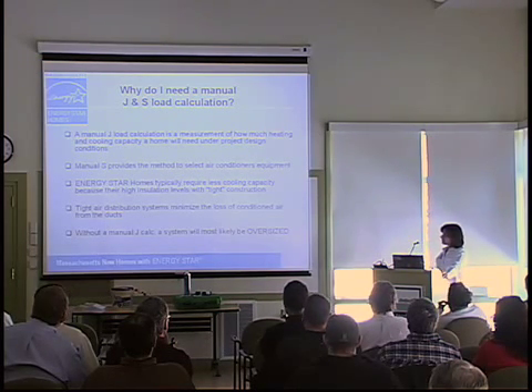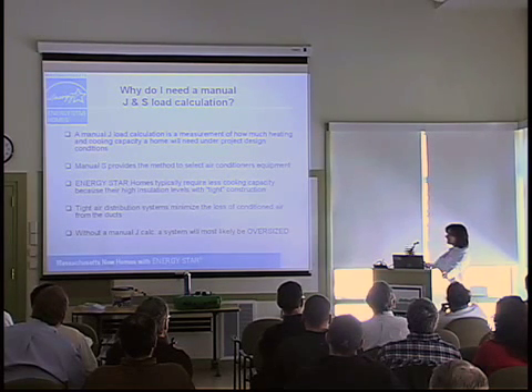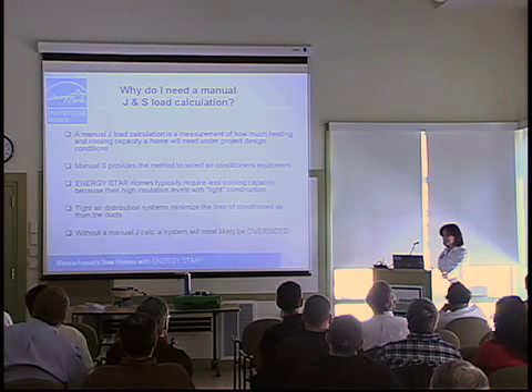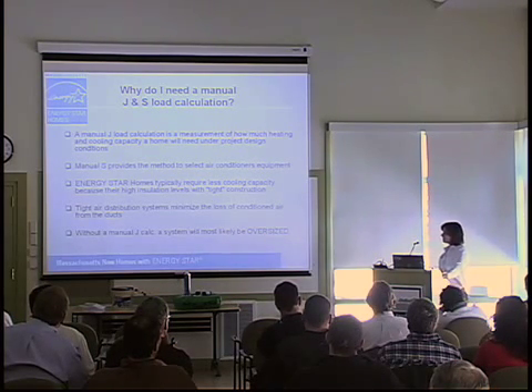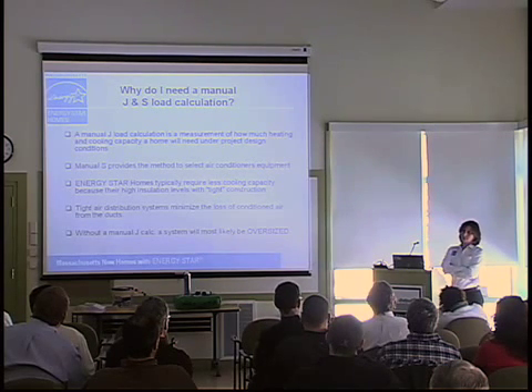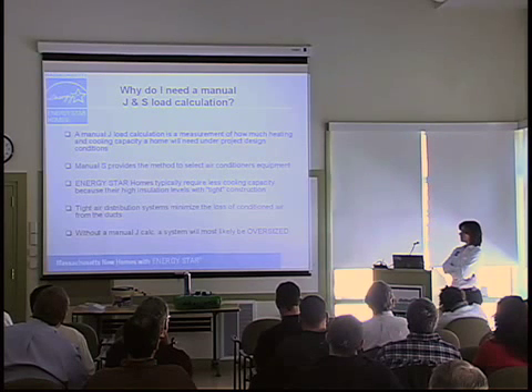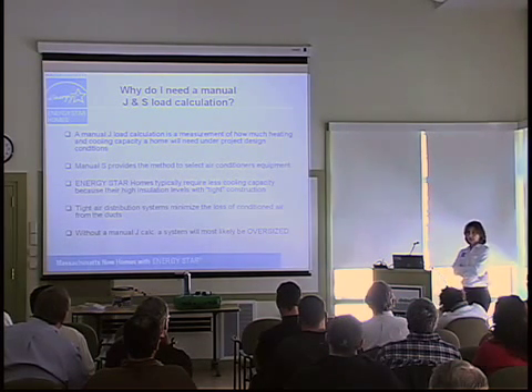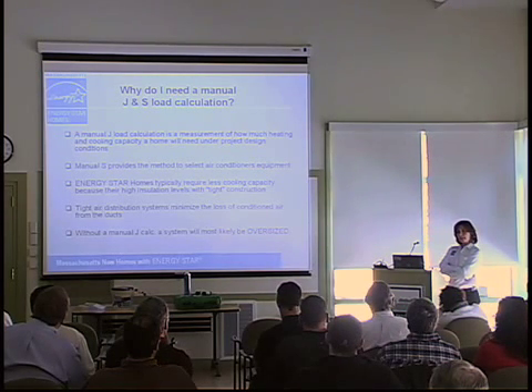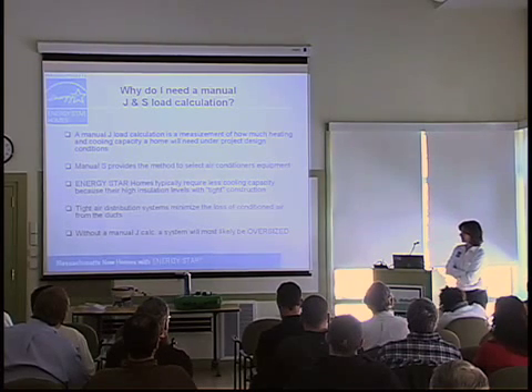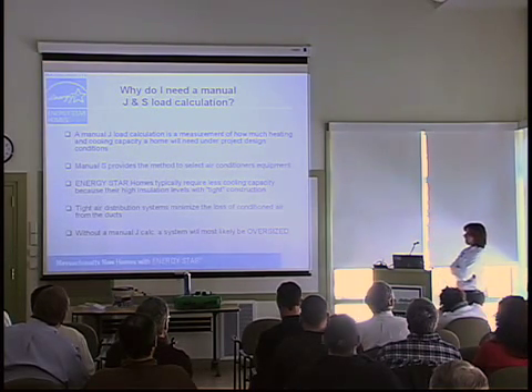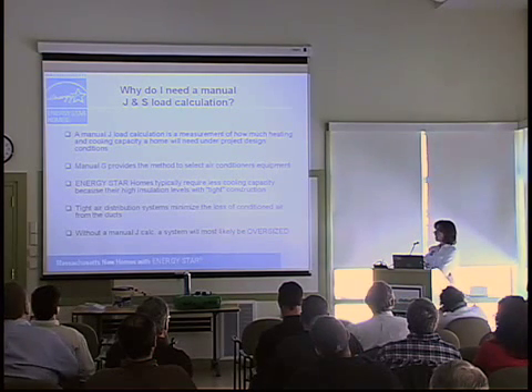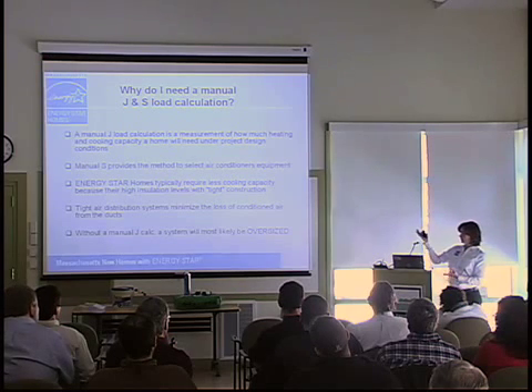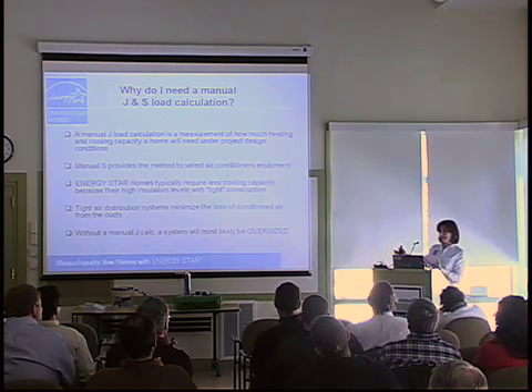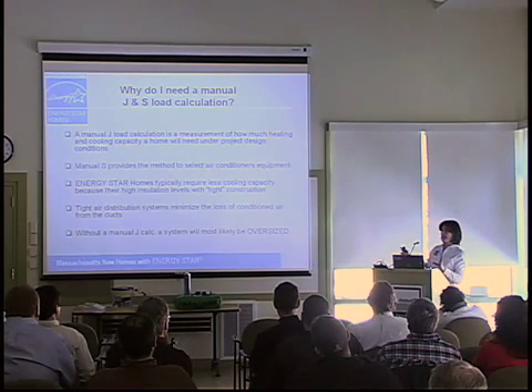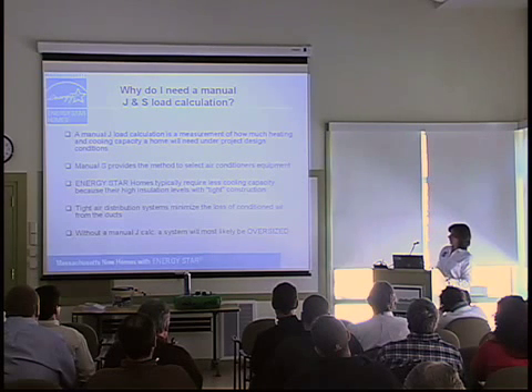A Manual S provides the method to select air conditioning equipment. This is, again, part of that ambiguous section of that requirement note, because you really don't need a Manual S in order to size equipment properly. There are a lot of other methods that are adequate that cooling contractors will use, but you might want to query your contractor or someone who's bidding on your job about what their method is. And again, I'll get into those a little bit later. But basically, if you were using software for Manual J, the software would just recommend certain types of equipment. You plug in the manufacturer and it would spit out the model numbers kind of based on the loads in that calculation.